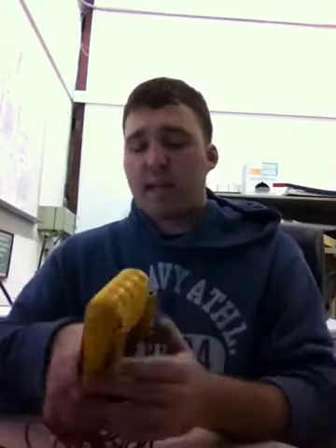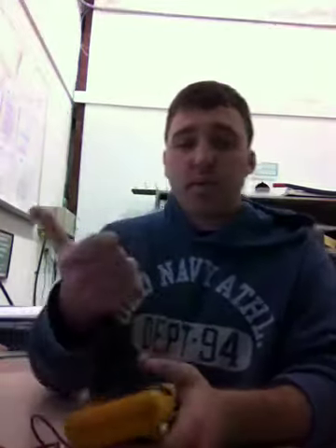And the last thing would be amperage, and this isn't one that has amperage, but a lot of them have clamp-ons. When the unit's running, you put it over your wires, and you can see what your amperage is running at, if you are running in the correct amps or not.